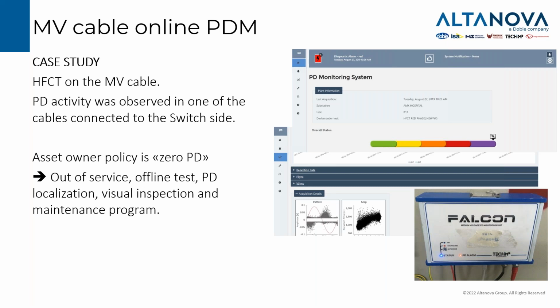So here is a good explanation of what we mean by designing the strategy for the results of the finding. For this specific company, the policy is to have zero partial discharge activities in the network.